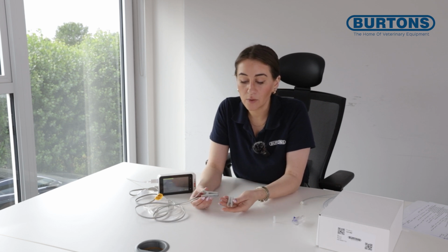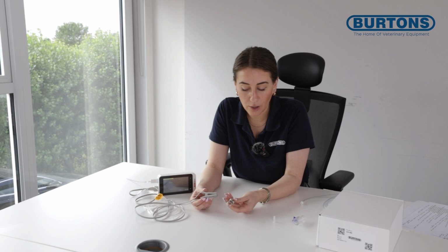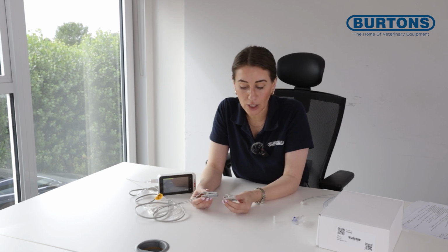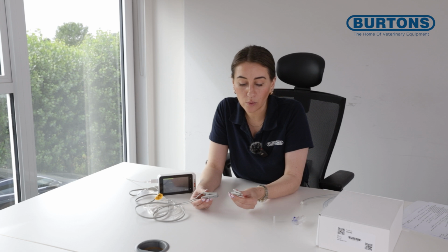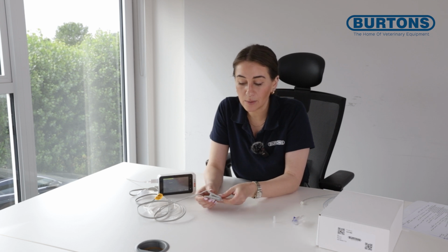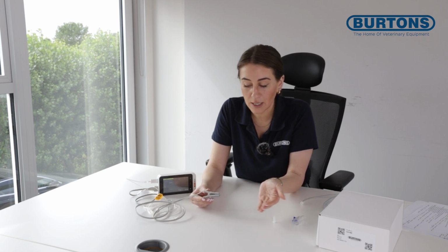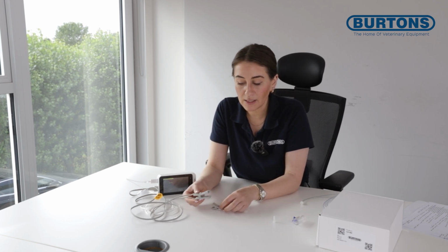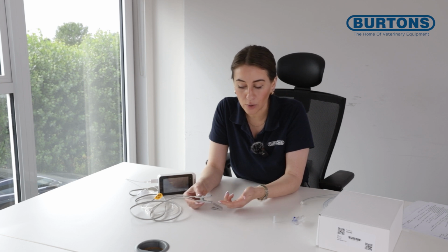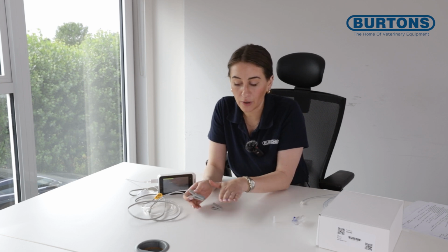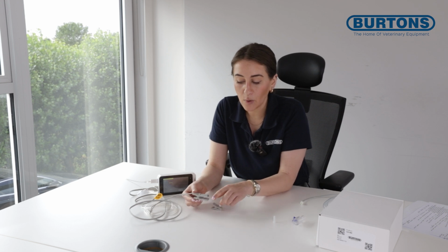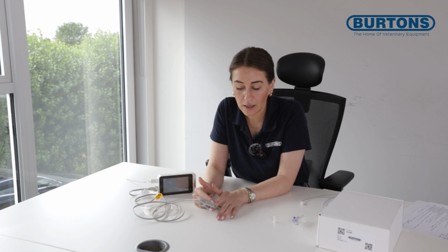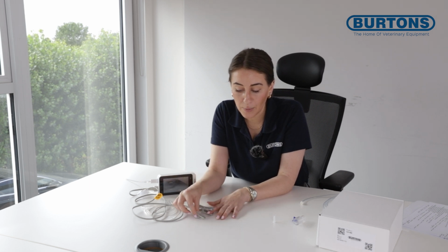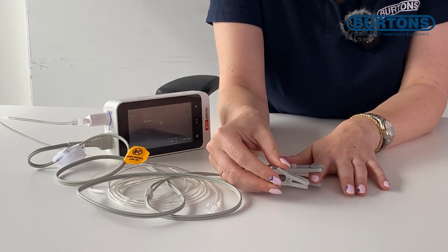So ideally we want to try and use the clip that is the least amount of force on our patient. So included in the machine is a smaller probe, which will put less pressure on tissue, and this is particularly important for patients, for example, that have received medetomidine and have peripherally vasoconstricted and therefore have less blood already. So if you imagine that this probe is causing a clamping action on tissue and essentially is blanching that tissue further away and reducing blood flow further. So ideally we want tissue that is nice and thick and not overly pressured by the probe itself. And if you feel that that's happening, you can obviously swap to the smaller probe that has less force applied.